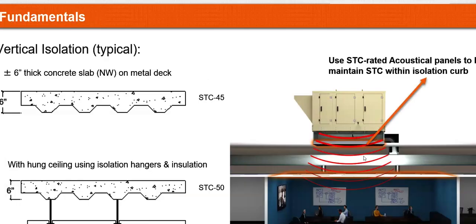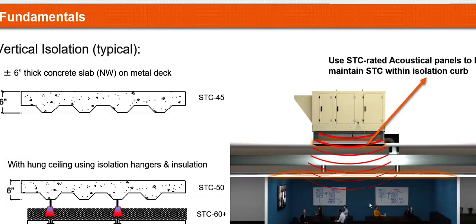An example of using sound transmission class in an application could be at the bottom of a vibration isolation curb. A lot of the times, the bottom of the curb, especially when it's bottom discharge, not so much when it's side discharge, gets overlooked. You don't have concrete decking below, and all of a sudden, you're dealing with a retrofit application, and the unit has to sit right above a meeting room, a classroom. Close attention needs to be paid when you're looking at such a scenario.